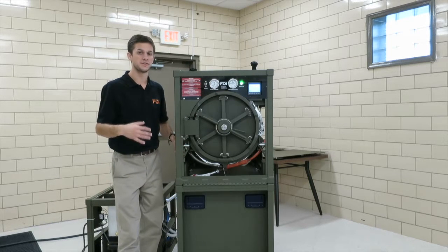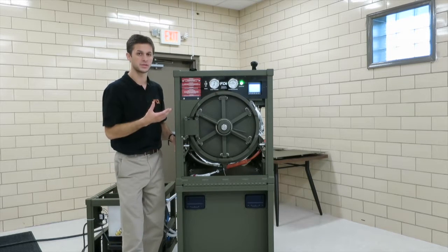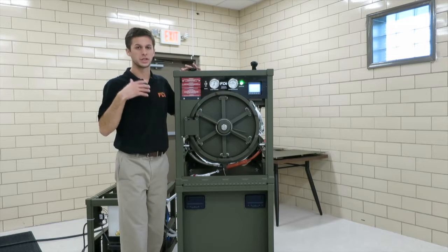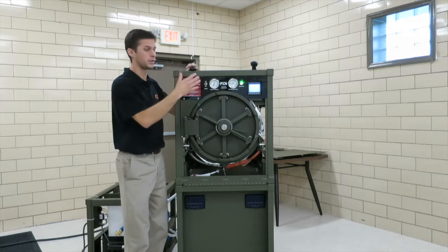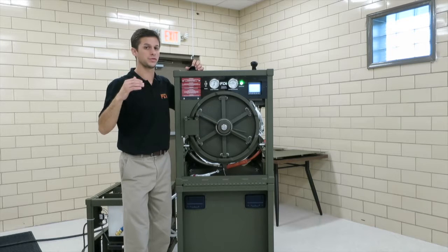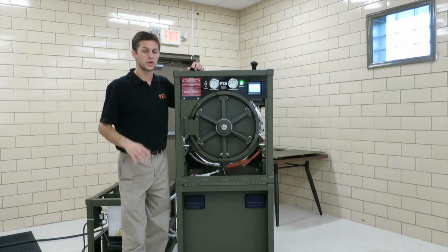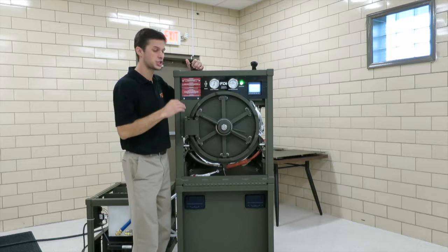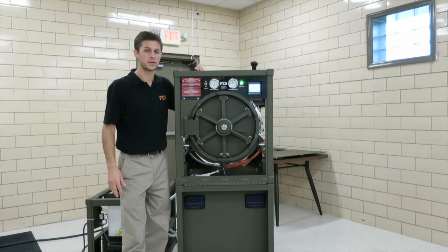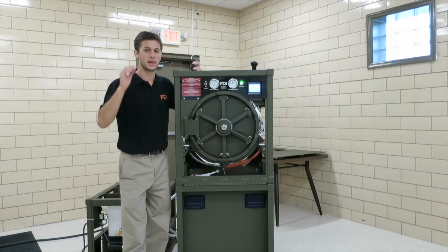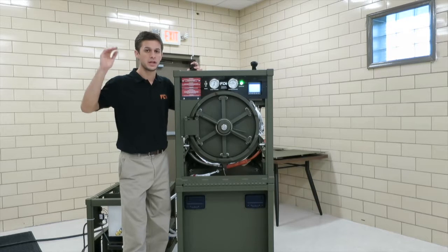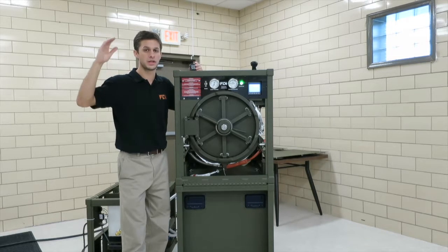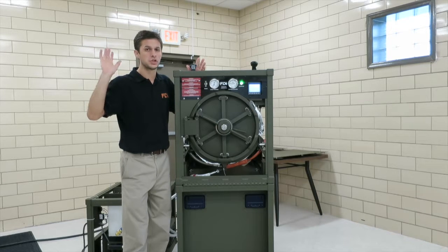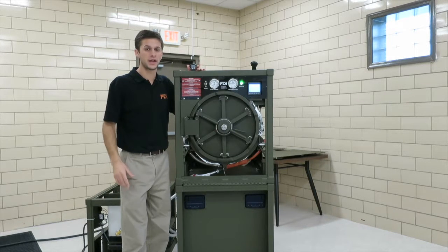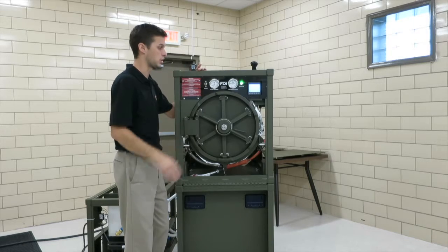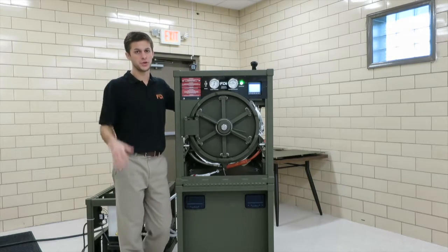So what we're going to try to do in this video is give you some tips on troubleshooting. What do these alarms mean? What is going on with the sterilizer when these 1 through 23 alarms come up? I'm not going to necessarily tell you what to check. You can reference the alarm section in your technical manual. For each alarm, it explains what's going on, and the top 2 to 3 things that you can check and fix to clear these alarms. So we're just going to march through them.